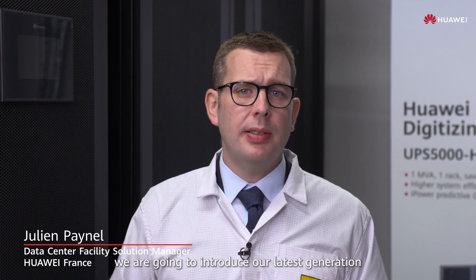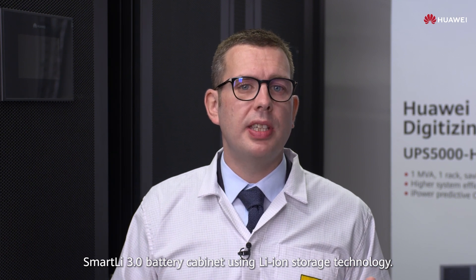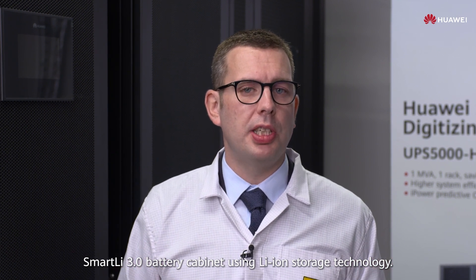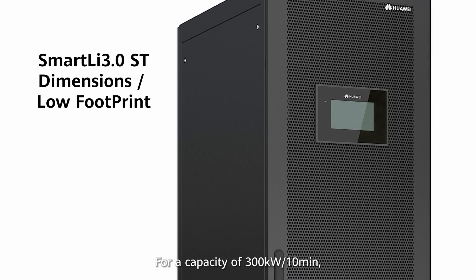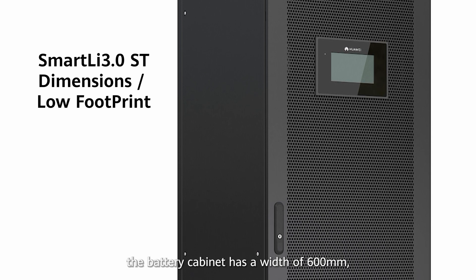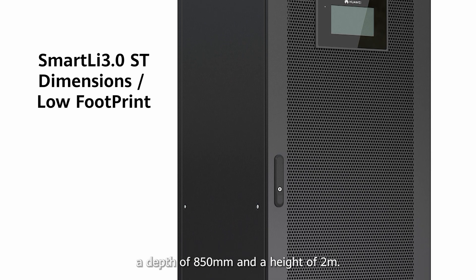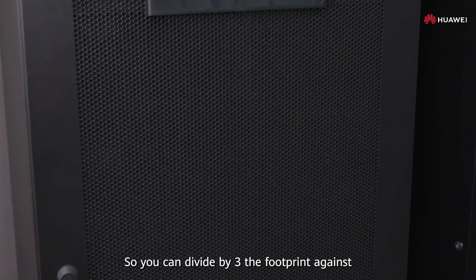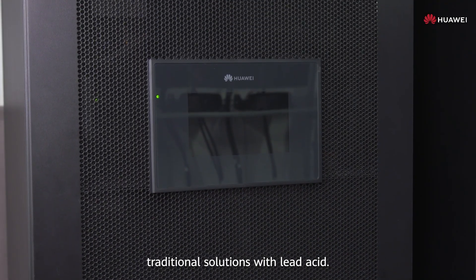In this video, we are going to introduce our latest generation SmartLi 3.0 battery cabinet using lithium-ion storage technology. For a capacity of 300 kilowatts 10 minutes, the battery cabinet has a width of 600 millimeters, a depth of 850 millimeters, and a height of 2 meters. So you can divide by 3 the footprints against traditional solution with lead acid.